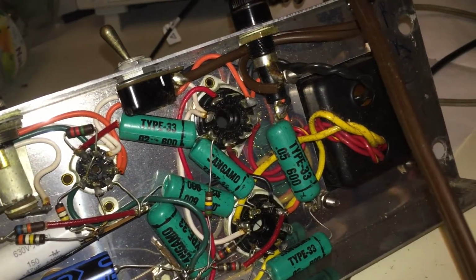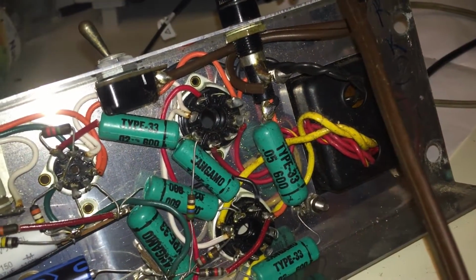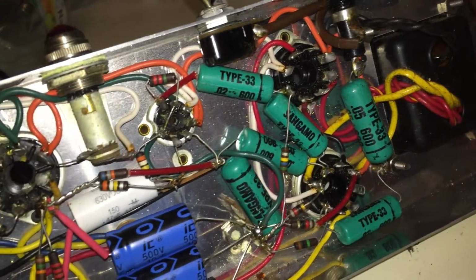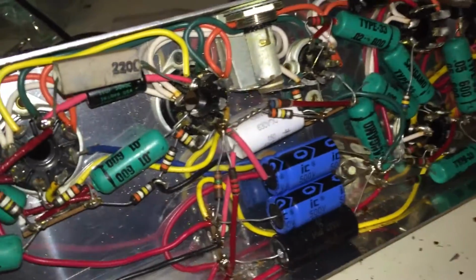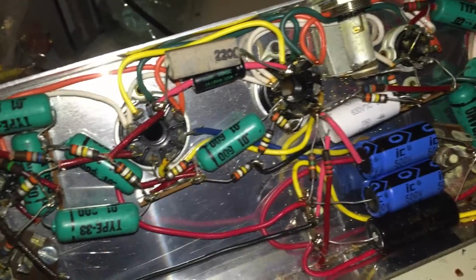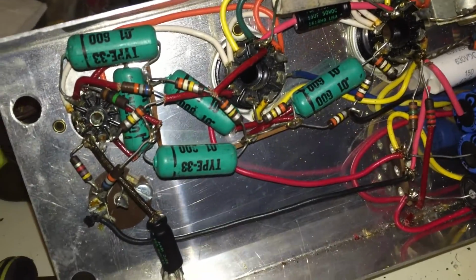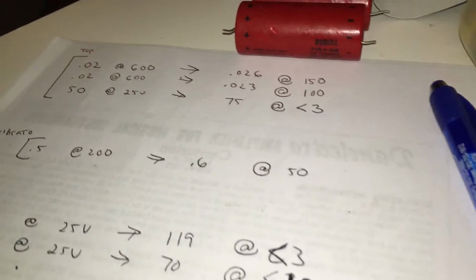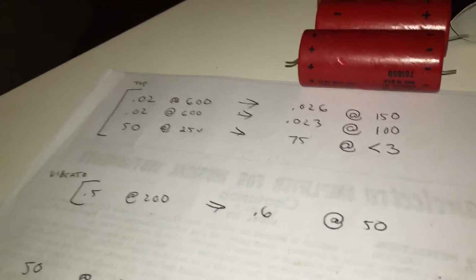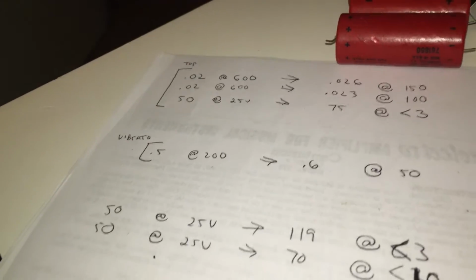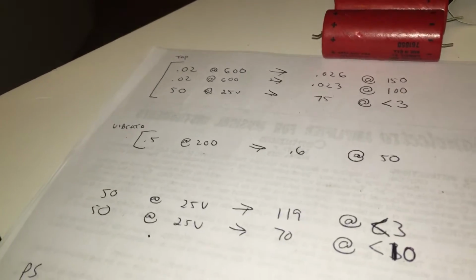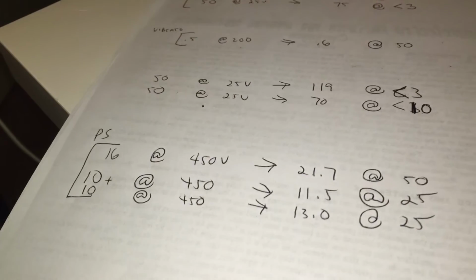The fact that they may be pulling down voltage, or the quality of the device may be suboptimal because it's been running like crap for so long, and people just assume that's how it's supposed to work, has absolutely nothing to do with the fact that when you have a component designed to be an open, and it's in fact shorted because of time, that component needs to be replaced. This is a testament to that.